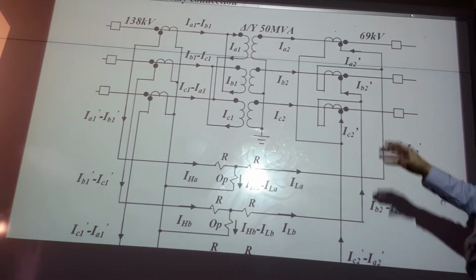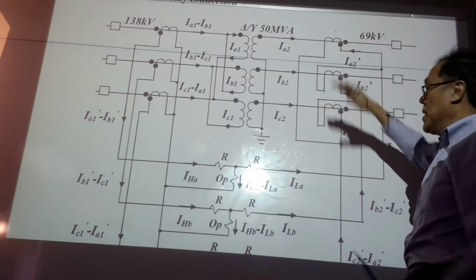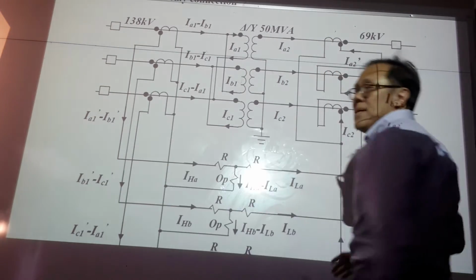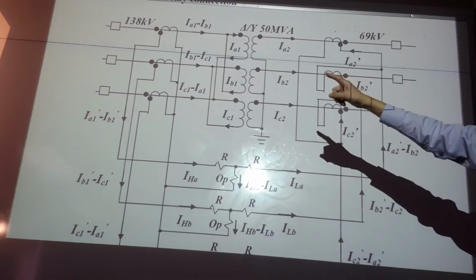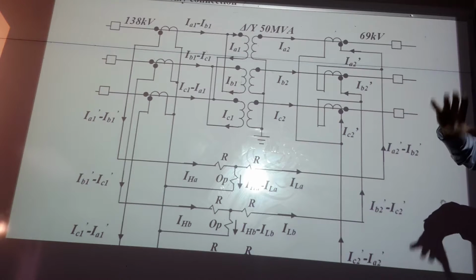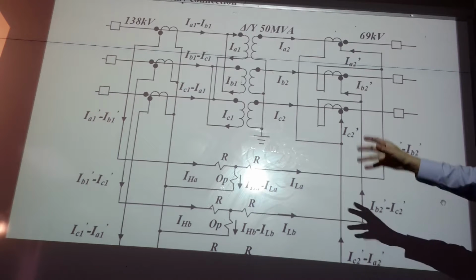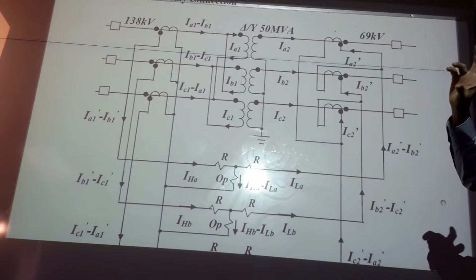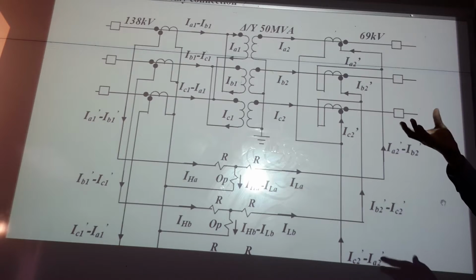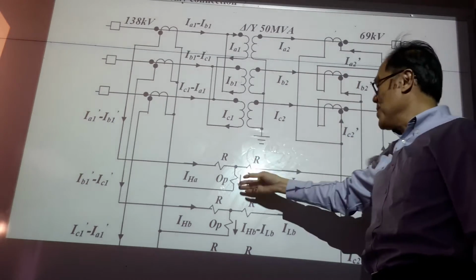Yeah, and we want that when this falls outside of this, it will not trip. So the quantity must be the same, but we have an issue because of this delta Y. So you have a √3 type of thing, and then you may not get exact cancellation. Yeah. And that's why we must use the delta to do the correction, such that even under external fault, it will not trip the relay.